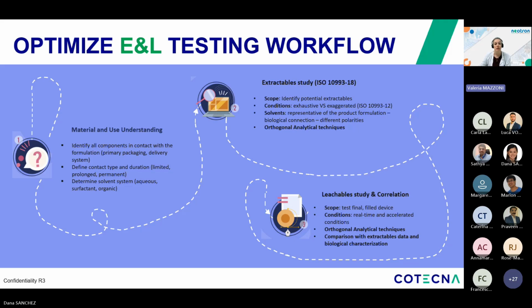Here, we can measure the actual compounds that migrate into the product or the patient pathway, generating exposure-relevant data that regulators rely on. And with no less importance, we must consider the correlation of the extractable and leachable results within the biological characterization. In fact, extractable and leachable data must align with cytotoxicity, sensitization, irritation, and systemic toxicity outcomes to demonstrate that any chemical exposure does not compromise biocompatibility.